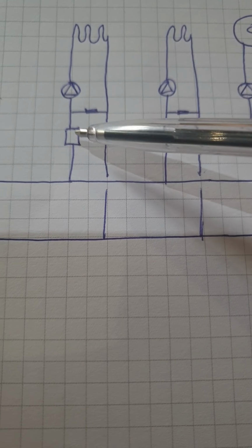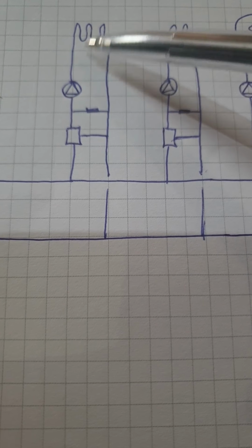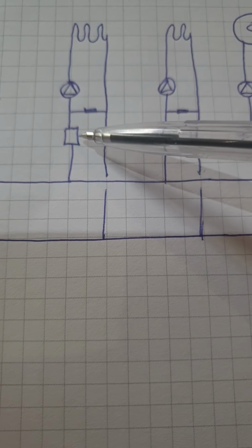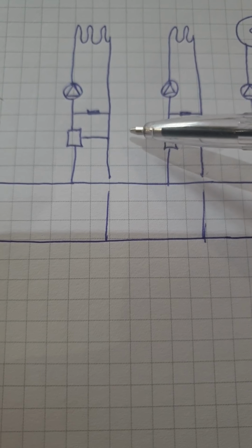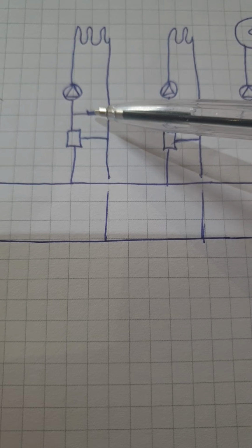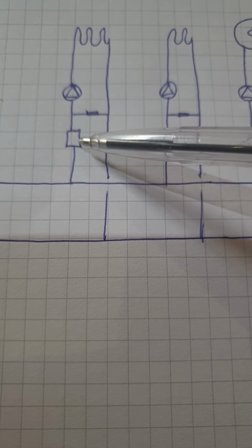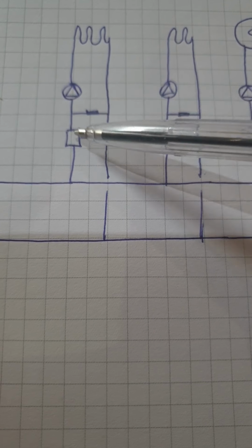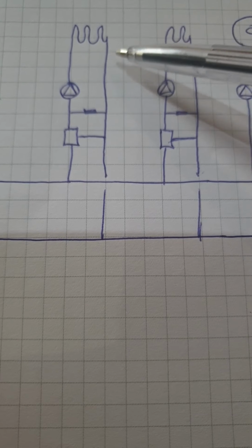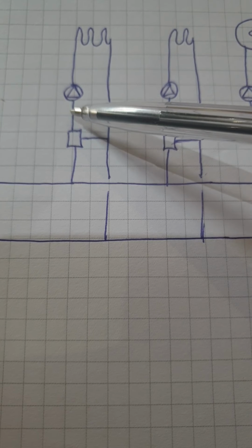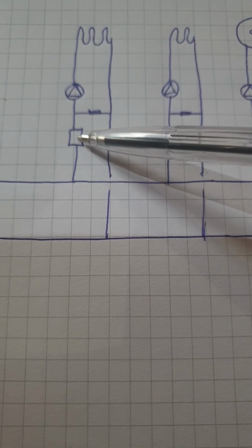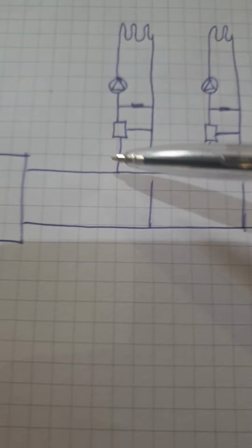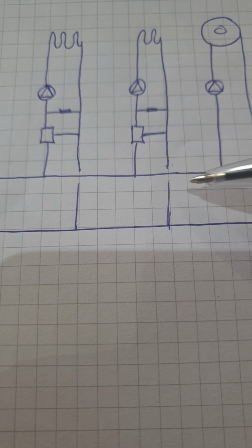We have our flow coming in, going through the mixing valve, hitting a pump, going through the underfloor manifold pipework and back, and there's a return off here to recirculate the return water. In the Viessmann drawings there is this bypass drawn in on many of them, and I think the idea of that is that it controls the maximum amount of water that can be drawn in from the flow. So let's say you've got a flow rate of 20 litres a minute on this circuit and we're always drawing 10 litres back, the maximum it's going to draw in from the circuit here is going to be 10 litres.